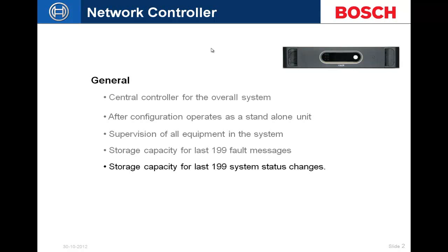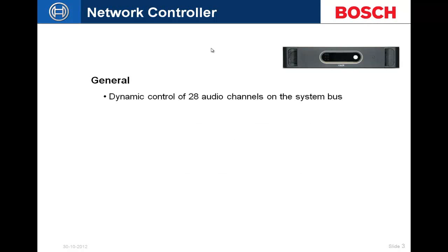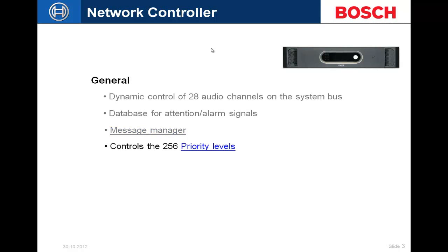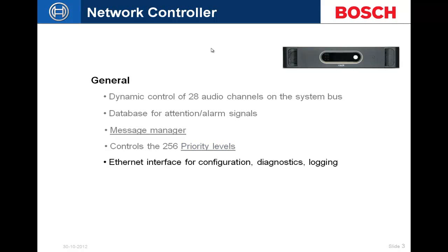It stores the last 199 faults and call events that happen within the system. Those can be recalled with our logging viewer and logging server software. It controls the audio — specifically, all 28 audio channels dynamically on the system bus. It's also the alarm and message manager. The NCO can store up to 1,000 individual message names with a total record time in WAV format of three hours, expandable to 12 hours if needed.